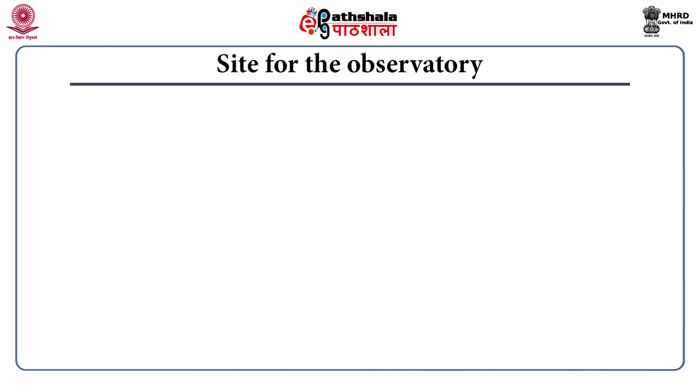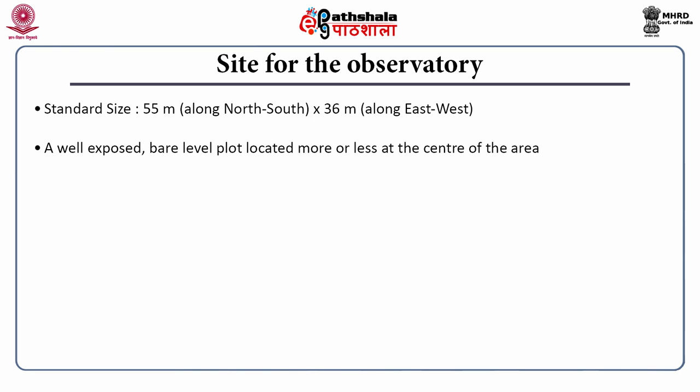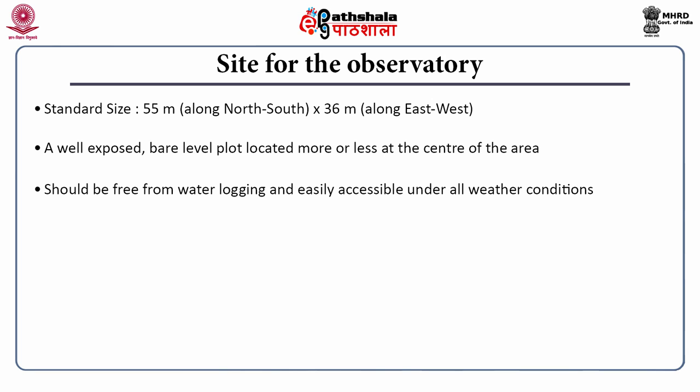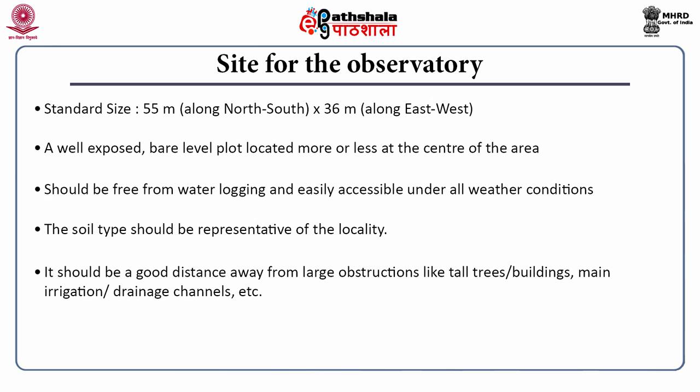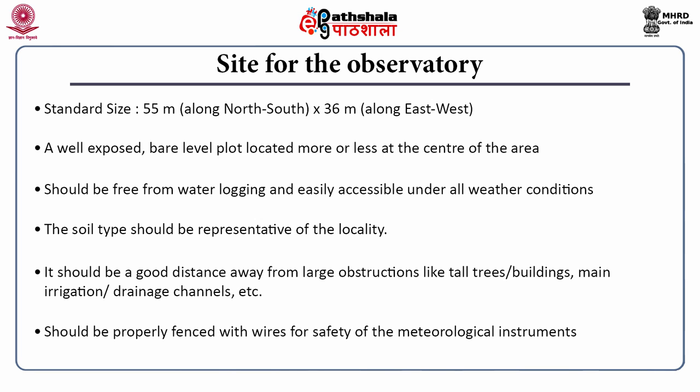What should be the ideal site for the observatory? The IMD, which is the nodal agency of weather observations and weather services in this country, has prescribed the standard size as 55 meters along north-south direction and 36 meters along the east-west direction. It should be a well-exposed, bare, level plot located more or less at the centre of the area. It should be free from water logging, easily accessible, and the soil type should be representative of that locality. It should be a good distance away from large obstructions like tall trees, buildings, and main irrigation or drainage channels. It should be properly fenced with barbed wire for safety of the instruments as well as for free air flow.